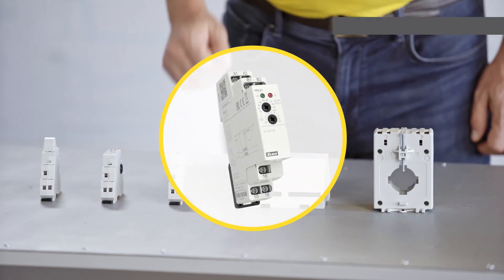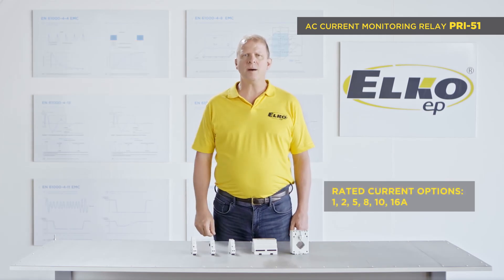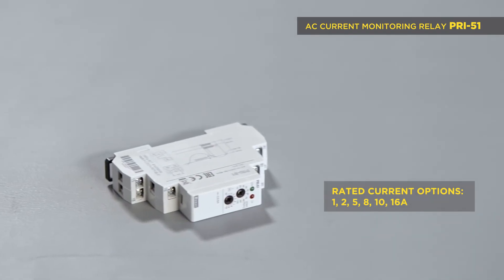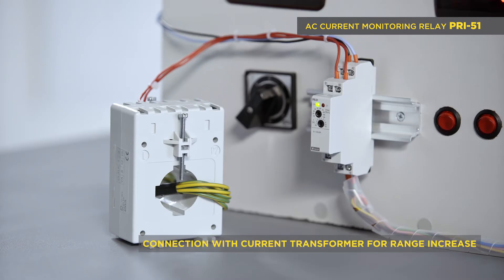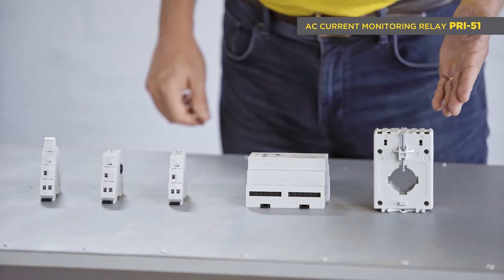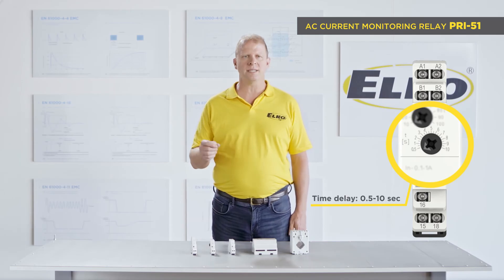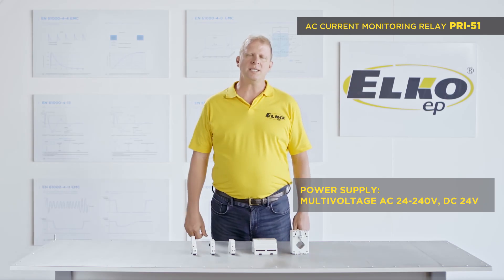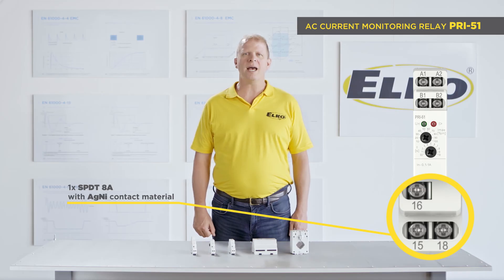PRI 51 is intended for direct current measuring via a built-in shunt. It is available in six options according to current range: 1, 2, 5, 8, 10, and 16 amps. The 5A option is intended for connecting to an external current transformer X5. The potentiometer has an adjustable time delay of 0.5 to 10 seconds for eliminating peaks. The supply voltage is multi-voltage AC 24 to 240 volts and DC 24 volts. There is one output relay with an SPDT changeover contact, 8 amps.